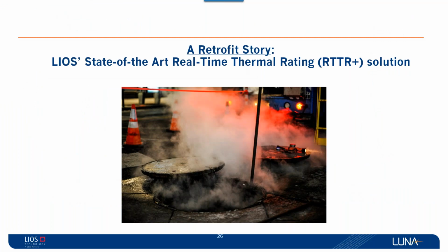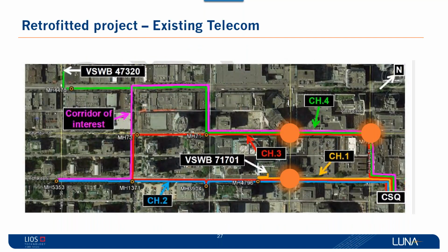So looking at this retrofit project was similar. Fiber optic sensing pulled already existing telecom lines from a substation, going to different routes and different substations. In this case, with the RTTR platform LIOS, automatically, where the DTS was installed at the substation, you have different routes where the DTS goes, and we can see the crossings of where the hot steam lines are below the duct banks. And these are strategically located.